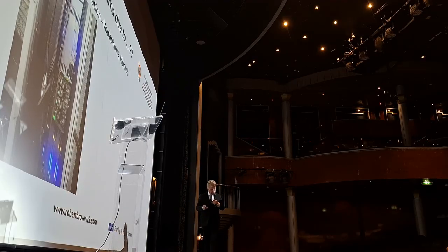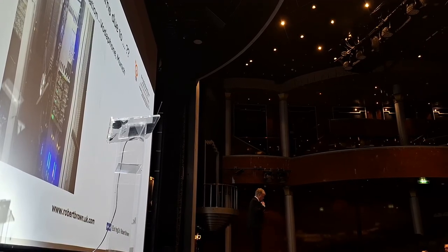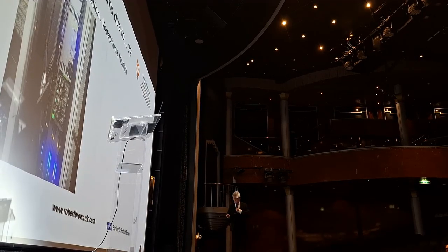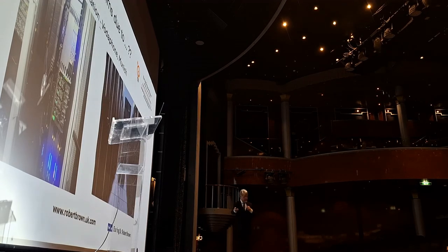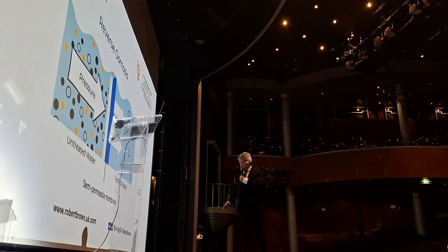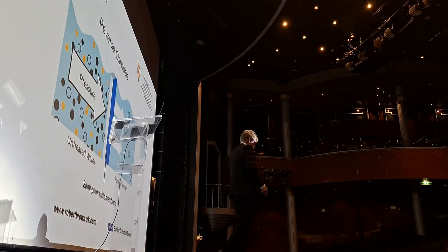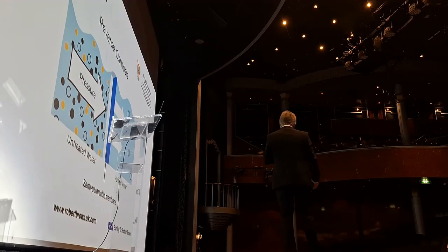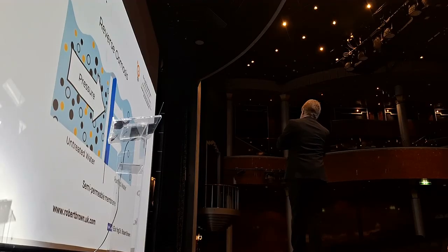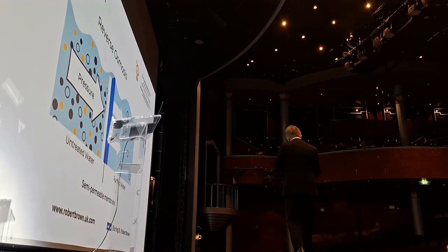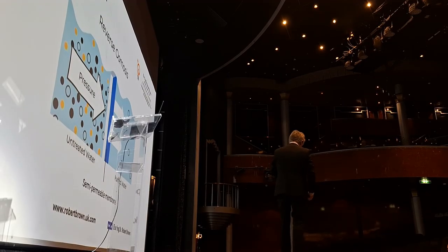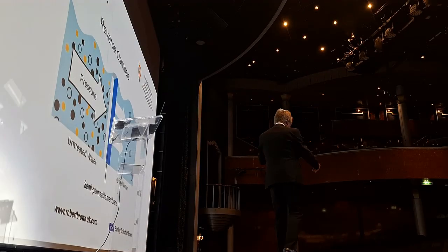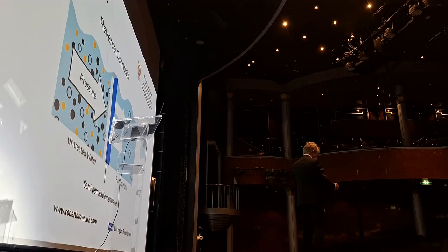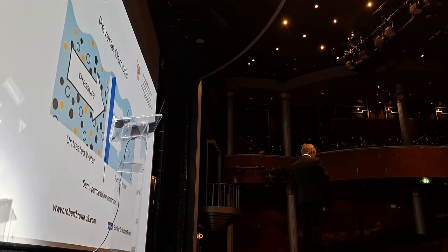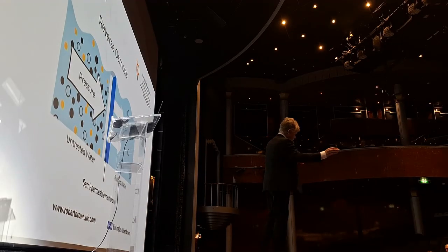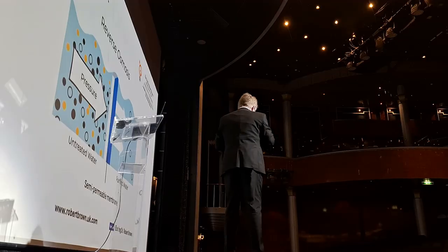And the grey deposits were not dust, because this was in a purified system in a room. What it was due to is the air inside the room, which was supposed to be purified via what we refer to as a reverse osmosis system, which is the system that takes out all the impurities from the cooling water, that failed. So the deposits on the front of these racks were salts, saline solution. So this had massive implications, because all these servers, with all your data, if you use Vodafone, were at the prospect of failing.